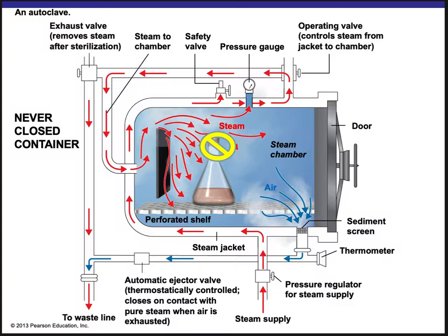Okay, so this is the autoclave I talked a lot about. I'm not going to go over all this, but the only thing I want to point out is, and they may have updated this in your book, I can't recall, but you should never heat a closed container. When you open it, it can splash the really hot liquid into your face.